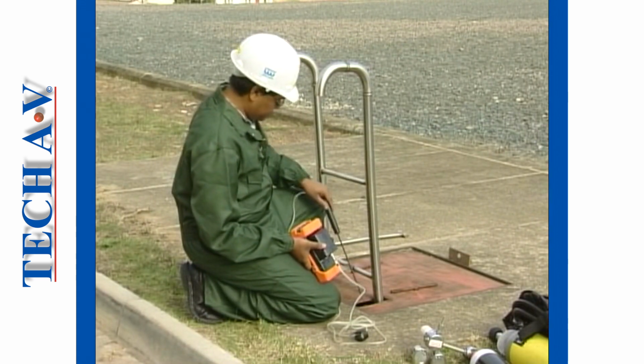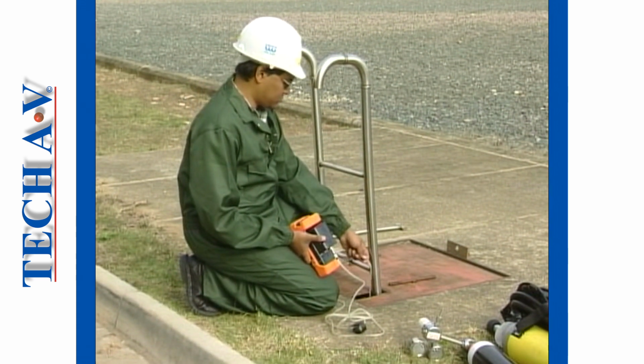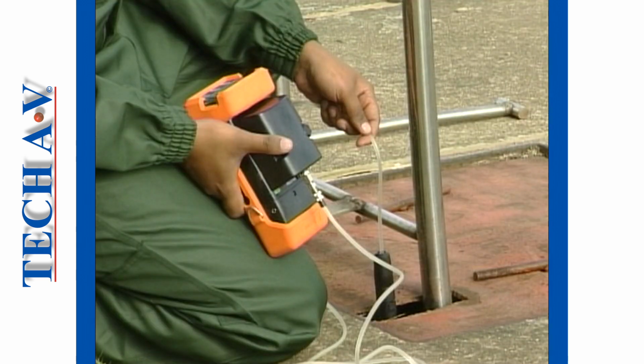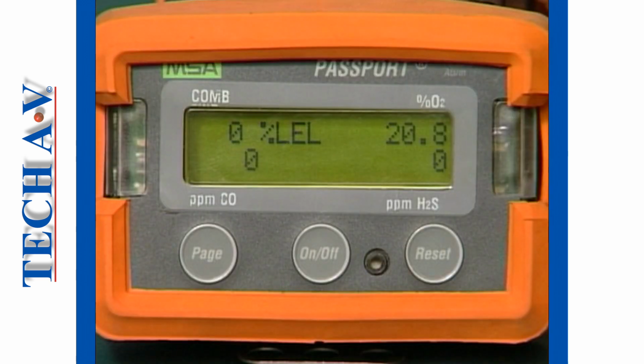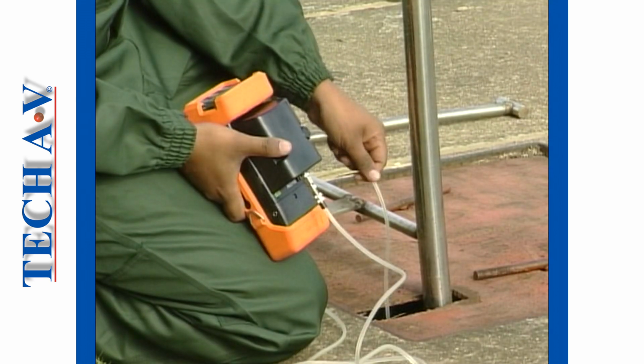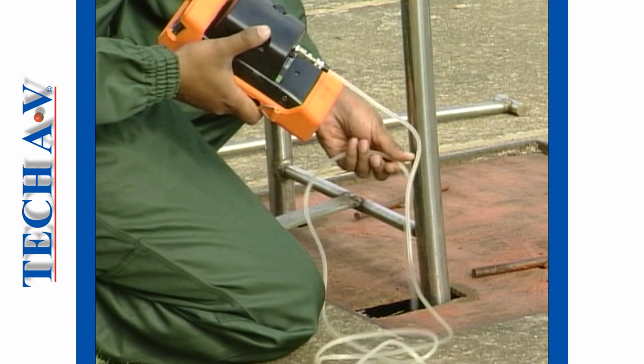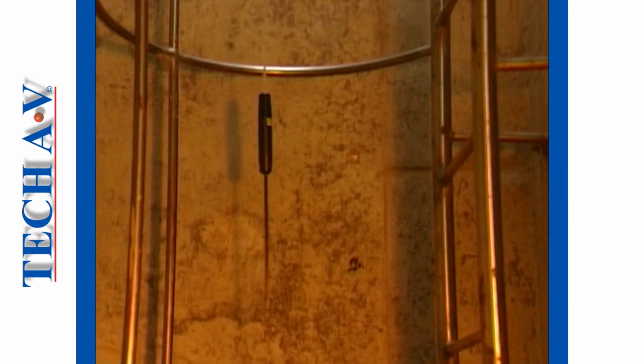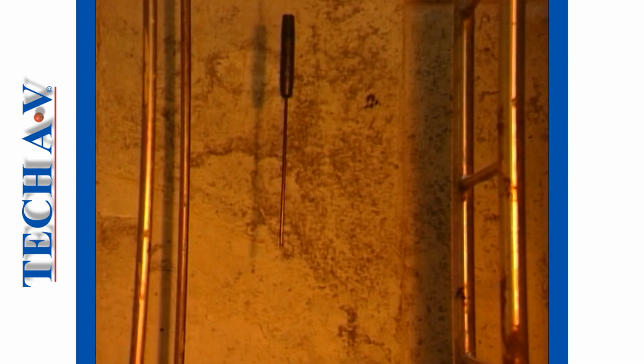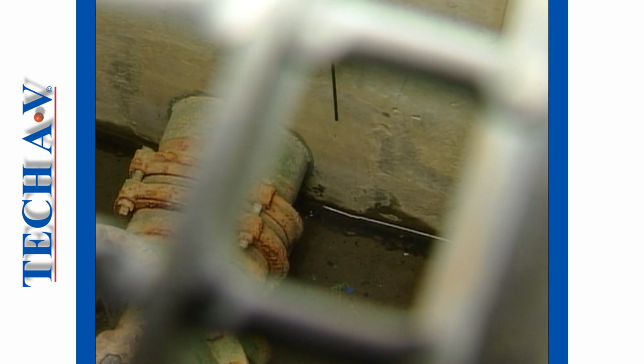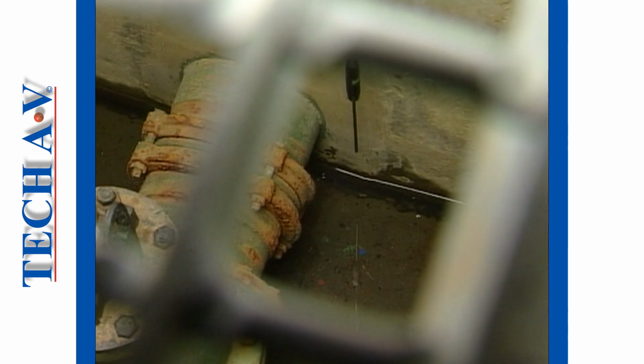Now the probe can be inserted into the space and then held still for a few seconds in order for the readings to stabilize. The display screen is now observed. In this particular application, we must assess the atmosphere at different levels in the space, as gases of varying densities could be present. In areas where water or sludge is present, do not let the probe enter this. Liquids entering a probe could be drawn into the instrument and cause damage.